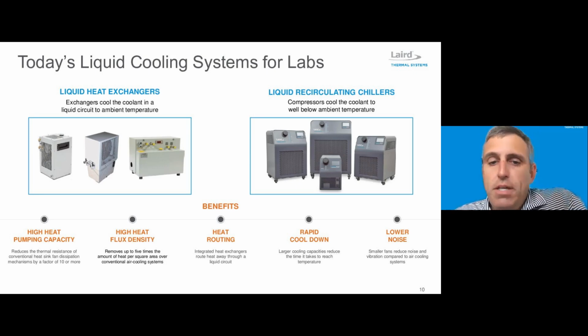These systems also, because of the high heat routing, can have a lower noise impact to the lab, either by being installed remotely, but at the same time, a lot of users like to have these close by. So a lot of the chiller manufacturers these days have taken this into account, especially in analytical applications, where we're trying to lower the noise of the actual system, whether it be the pump, the compressor, or the condensing fan. And I'll talk a little bit more about that in a minute.